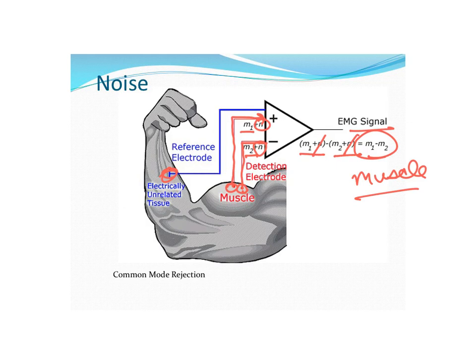Finally, to end, I just want to make sure I mentioned that this concept of having two surface electrodes is called the common mode rejection. What you are doing is rejecting or subtracting out what's common to both electrodes, which is the noise. Sometimes it's CMRR or the common mode rejection ratio.